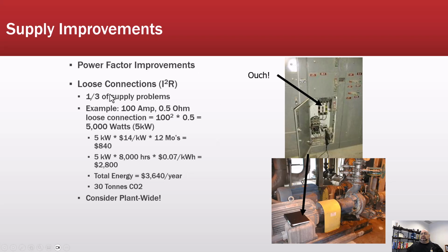Supply improvements. So in addition to power factor stuff and so on, actually power factor doesn't reduce energy costs. It improves the capacity that you'll have in a facility. It'll do some other improvements. It will reduce some very small I-squared-R losses overall. It does have a downside though. Apparently, when we have high harmonics in the system, my power factor correction capacitors become a load, increasing my costs even more. That's something we're going to cover in the future as well.